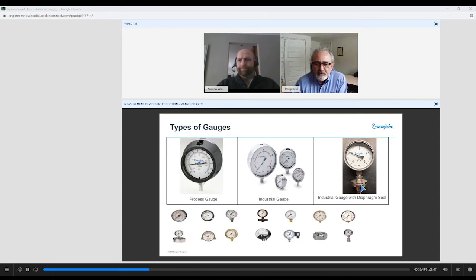We look over here, we have an industrial pressure gauge with a diaphragm seal, otherwise known as a chem seal. And what this does is this separates the media from a fill media that would be put into the Bourdon tube, a very specific amount, and this will have a chemical barrier, and that's a diaphragm. It can be exotic alloys, it can be Monel, there's various things, titanium, barriers in there, or it can be plastics, it can be a polymer, it can be PCTFE or something else.